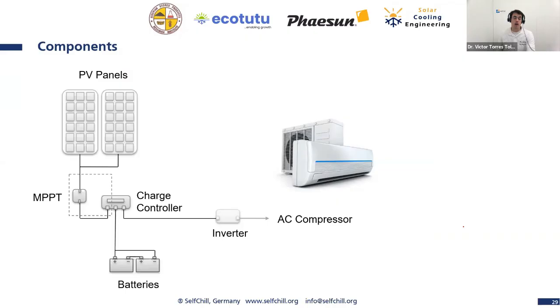So in the next slides, we are going to have a look at the components. You have seen already a heat pump, you have seen the PV panels, but what else do we need? So if we, for example, take a conventional heat pump, so imagine we are using just a conventional air conditioner for our cold room or for any kind of cooling system, then we might have an AC compressor. And if we have an AC compressor, as you know, we need an inverter to be able to run the AC compressor at 220 volts, AC current, 50 hertz, and be able to provide that with DC current. So if we have, for example, here 2 batteries at 24 volts, then we have here DC current, and we convert it into AC. I think this is well known by all of you.